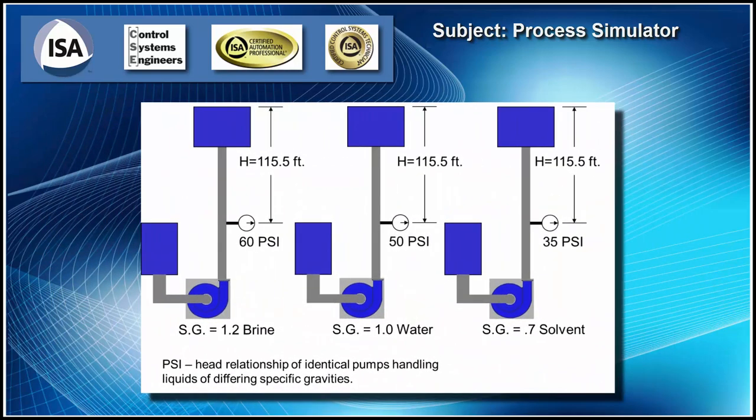So remember, specific gravity is the weight per volume of a liquid over the weight per volume of water. And with gases, it's the gas or vapor weight per volume over air weight per volume. And these have to be referenced to standard references so everybody has the same reference. So water and gas will typically be 60 degrees Fahrenheit and 14.7 PSIA. So make sure that it's 60 or 68 degrees or whatever reference you're using. There are multiple references out there for standards.